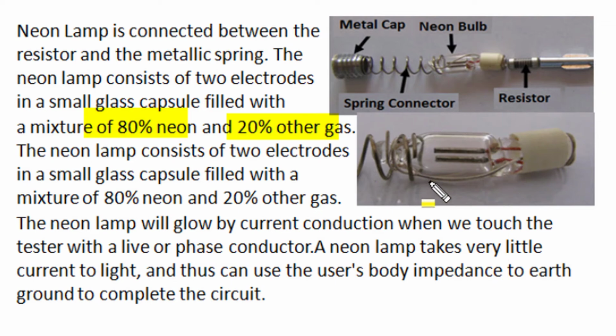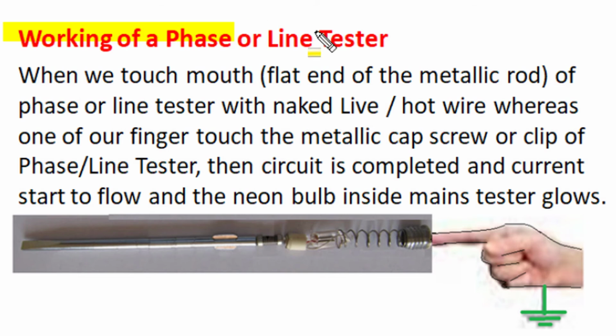A sensitive neon lamp takes very little current to give light output, and that current, less than 1 milliampere, can be withstood by the human body. So we can use human body impedance for testing purposes in such neon lamp circuits without risk of electric shock to the human body. The working of a phase or line tester, or neon tester, is very simple.